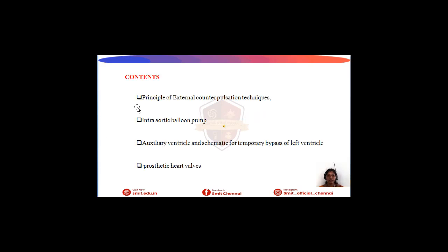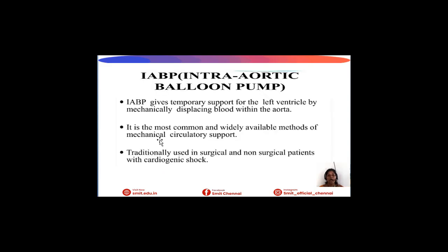In this, we have seen already the principle of external counter pulsation technique. Today we are going to see about the intra-aortic balloon pump, that is IABP. It is a mechanism that gives temporary support to the left ventricle of the heart by providing mechanical support to the left ventricle through a balloon within the aorta. It is a widely available method for supporting the left ventricle. It is an invasive technique.